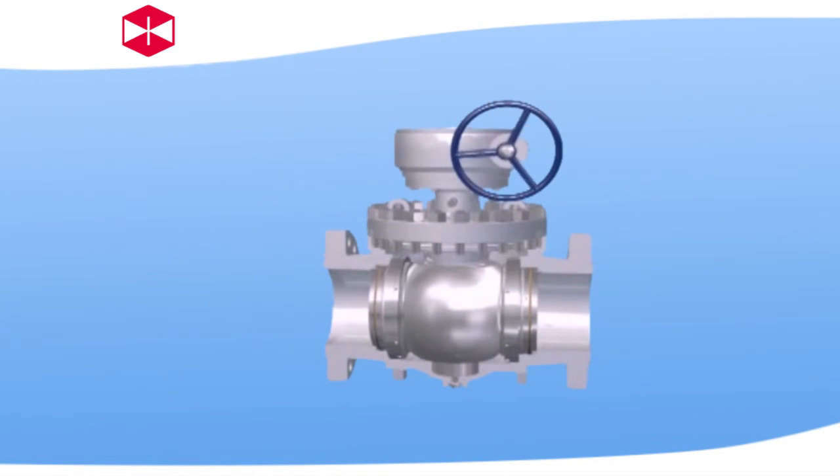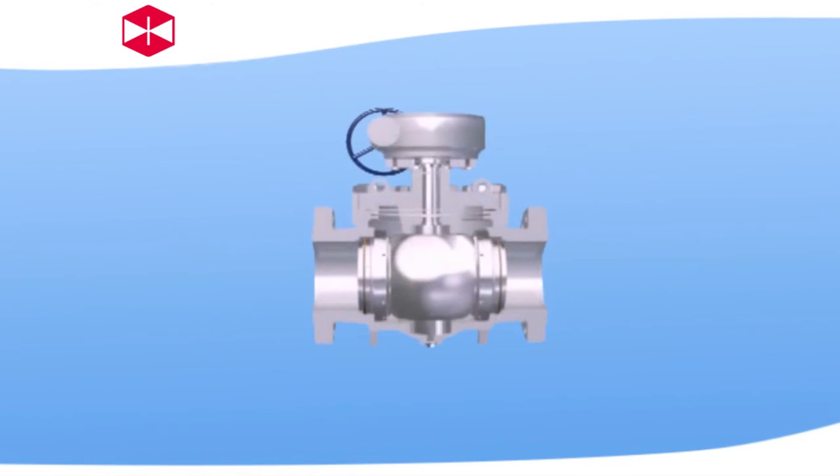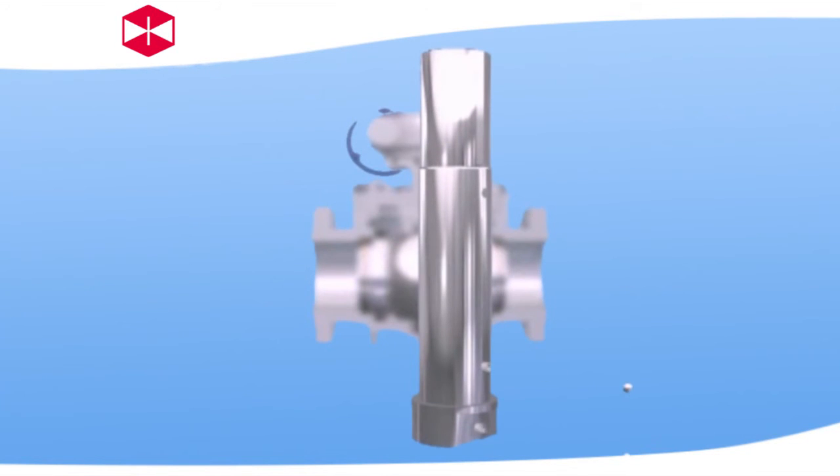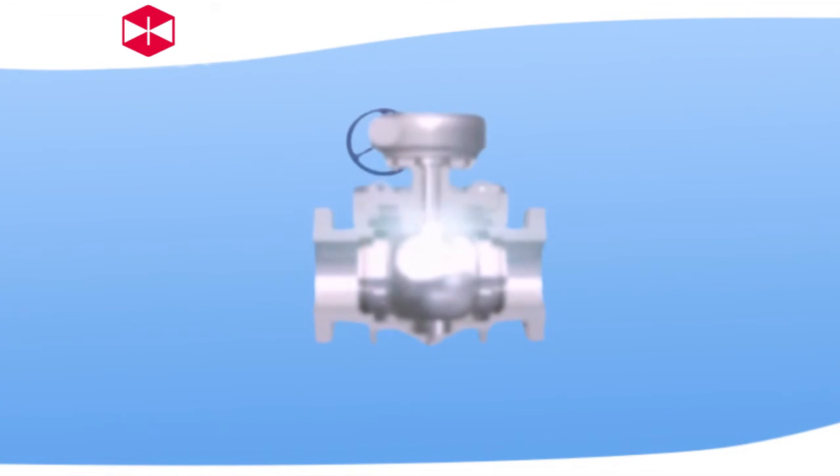Valve anti-static device. When operating the valve, the frictions between the ball and the non-metal seat reproduce electrostatic charge. But it can be accumulated on the ball to prevent static spark. An anti-static device is placed on valve to derive the electric charge accumulated on the ball from the static channel between the ball and the stem or between the stem and the body.